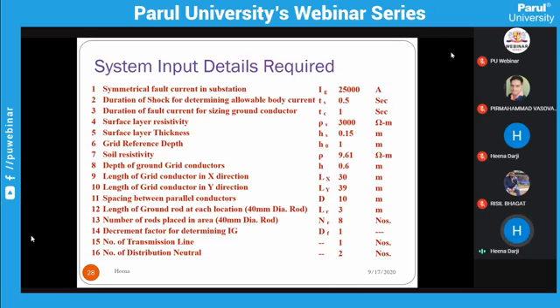Now, the duration of shock for determining your allowable body current. We have already checked this. For the human body, your fibrillation time is 0.5 seconds. So this duration of shock is 0.5 second. Now the fault current for sizing the ground conductor. Your conductor's fault current duration is 1 second. Now surface layer resistivity.